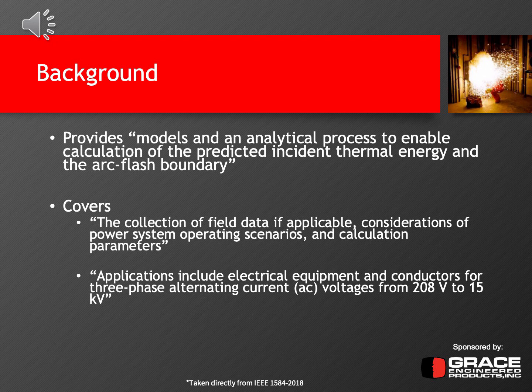It also provides arc flash boundaries, where a worker or maintenance personnel or whoever is doing the work needs to rope off and secure the area so that any non-qualified person doesn't encroach into the arc flash boundary, especially without wearing PPE, which minimizes any damage to that non-qualified person. It also provides guidance based on the incident energy levels. One can use NFPA 70E or other sources to determine personal protective equipment requirements for the person at that panel, or wherever they're doing work, to properly protect themselves based on these calculations.